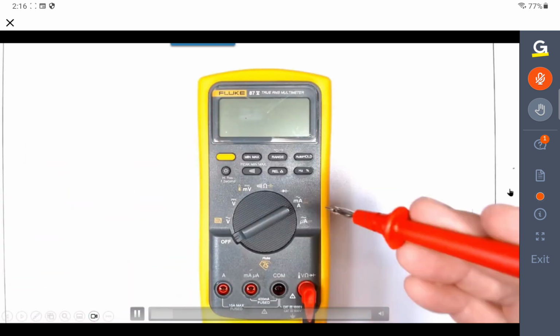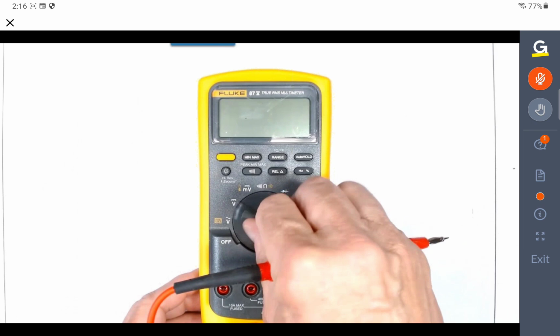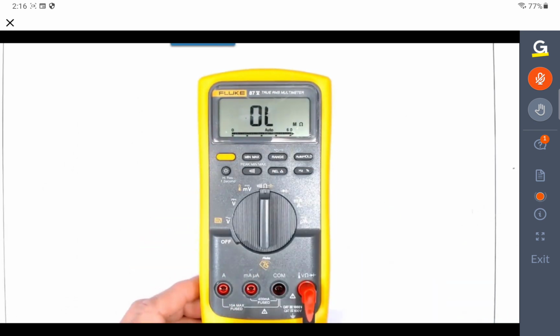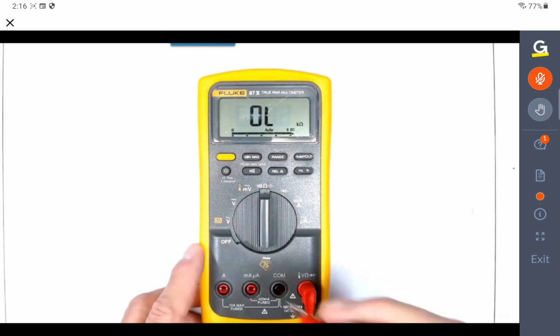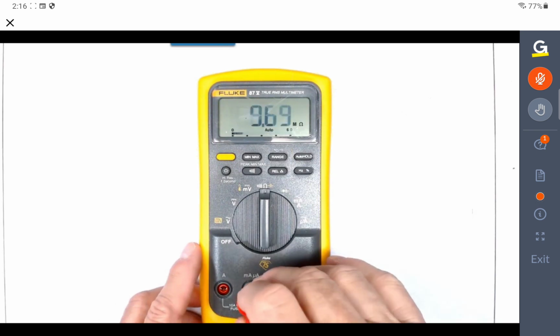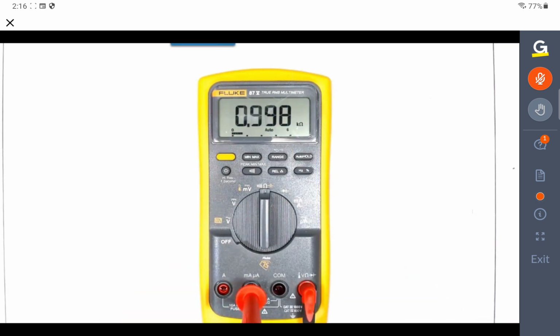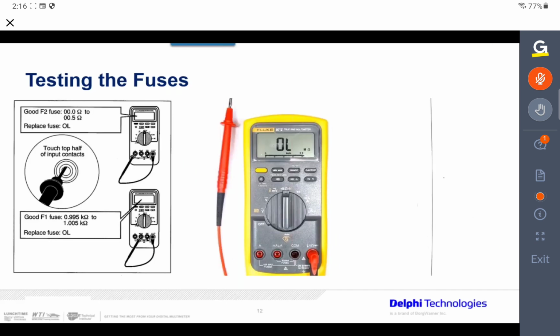One lead, and I'm using a 4 millimeter banana type plug on the end there instead of the other one. If I was using the other style, I'd have to pull it up and touch. Notice there's a lead and it says 0.1. I am within range. It is good fuse. And I do this one lead. It says 0.99, 0.98. That means I'm in range. That fuse is good. So I know immediately I can check amperage without giving me false readings. So it had to be 0.995 to 1.005. Both of the specs are good. Got good fuses in the system.